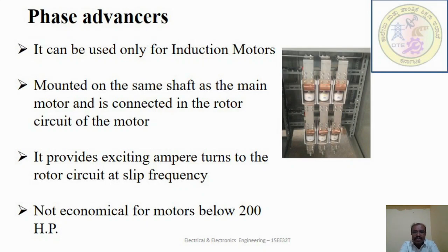How are the phase advancers used? The phase advancers are mounted on the same shaft as the main motor and connected in the rotor circuit of the motor. It provides the exciting ampere turns to the rotor circuit at slip frequency. By providing more ampere turns than required, the induction motor can be made to operate at a leading power factor, like an over-excited synchronous motor.